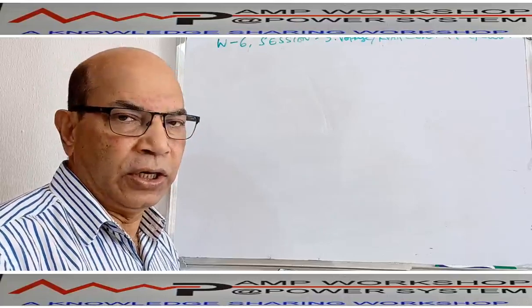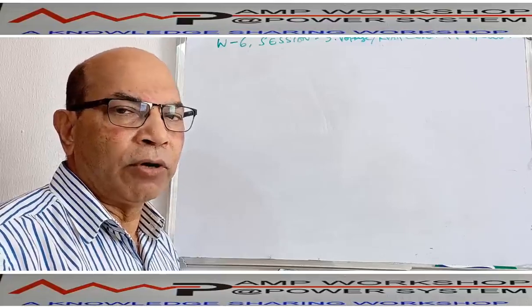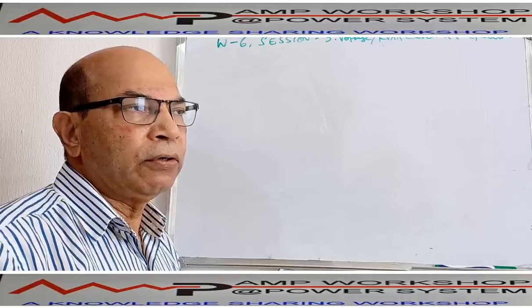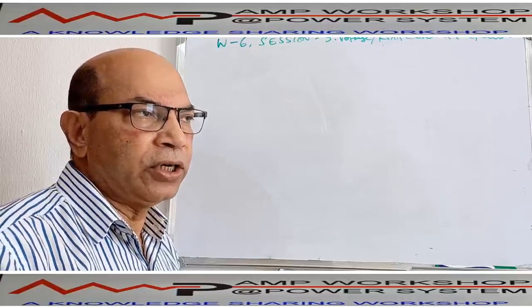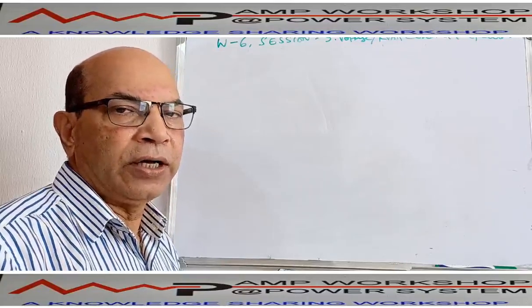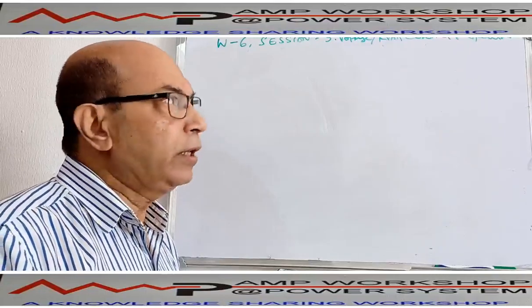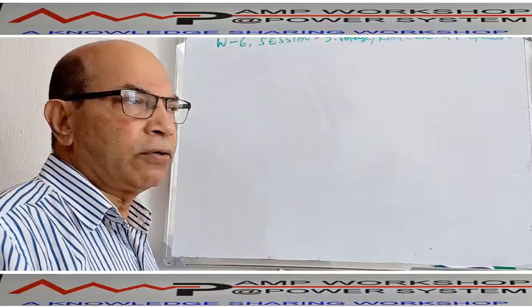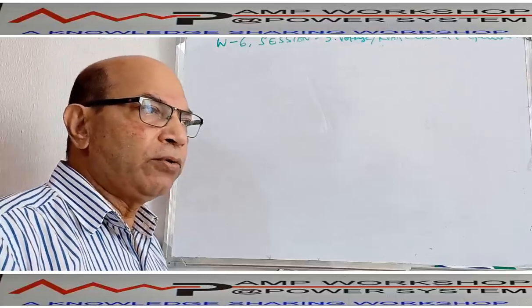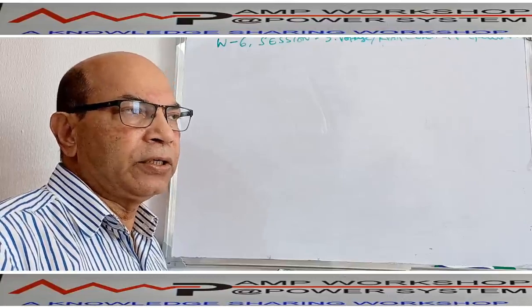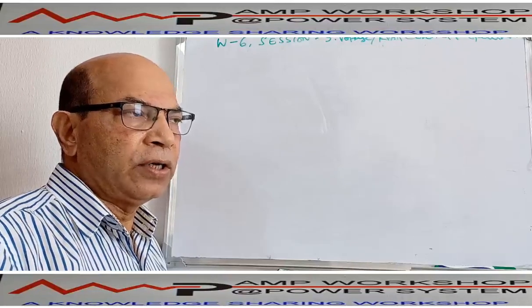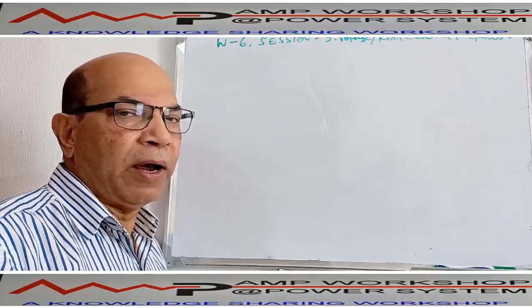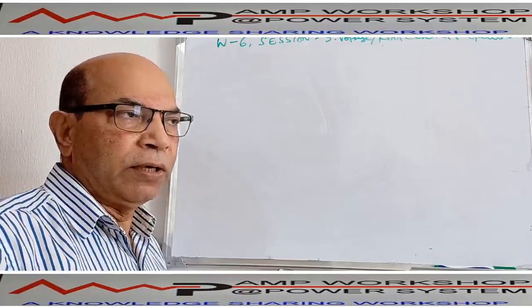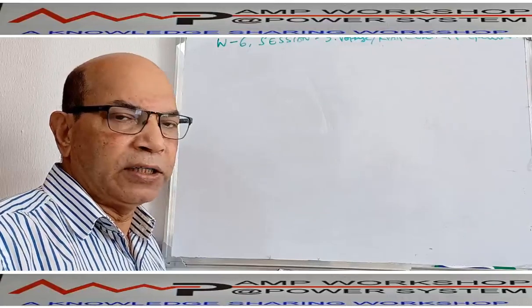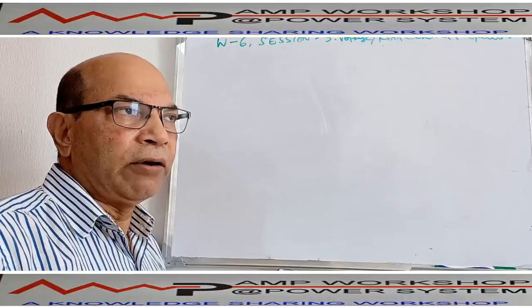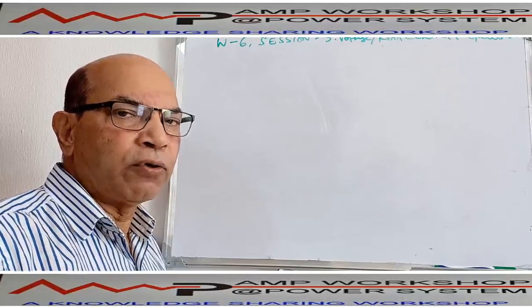So today's session 3, we will try to cover voltage control or VAR control of a generator, whether it is a single generator or multiple generators running in parallel. So that will be our topic today, that is voltage or KVAR control of generators. Before going into the control of this parameter, we have to discuss first how this parameter is generated by a generator. If we know the process by which the voltage or VAR, or reactive power, is produced, then only we can find the way to control it.